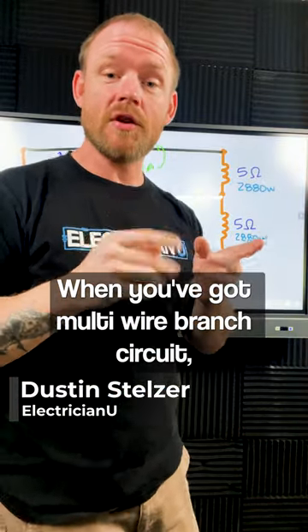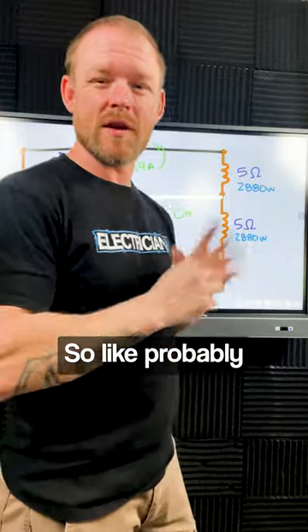When you've got a multi-wire branch circuit, you have two hots and a neutral. The neutral is shared, so probably a piece of 12-3.